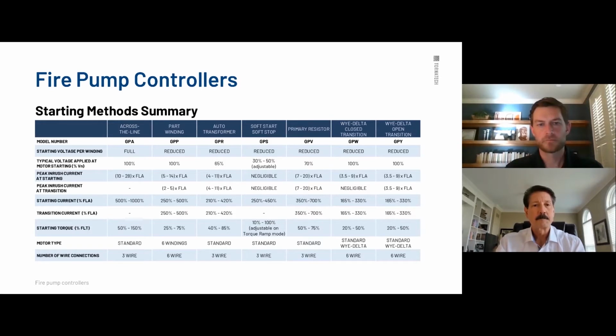Auto transformer. Auto transformer has been around, it's been steady Eddie for decades and decades and decades, well before my time. And really it's a hunk of iron. It's a transformer that typically pulls off taps at 65% voltage. It's reduced voltage, probably 3.5, 4 times full load amperage you'll see on the inrush. It does a great job. It really is something that doesn't break down. It emits heat in the wintertime, keeps your controller warm, obviously. That technology has predominantly been used quite a bit through the US, but really in Canada.